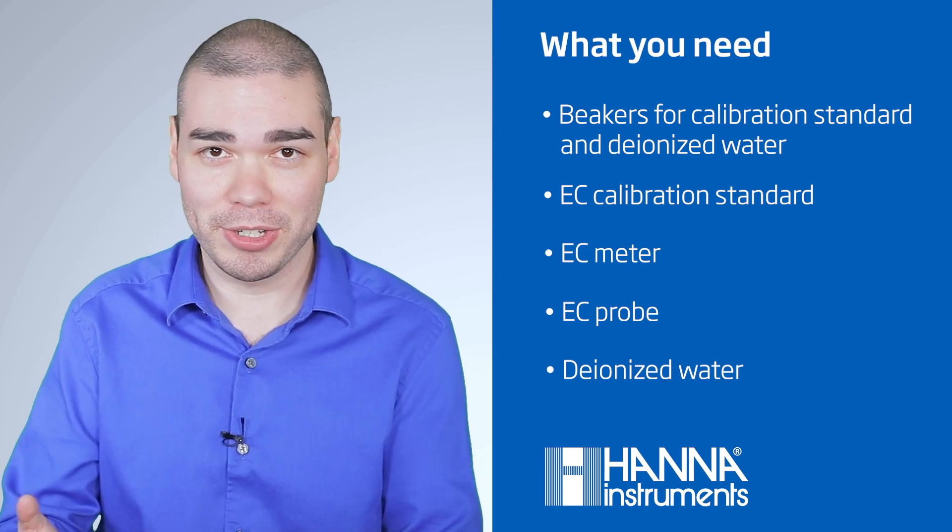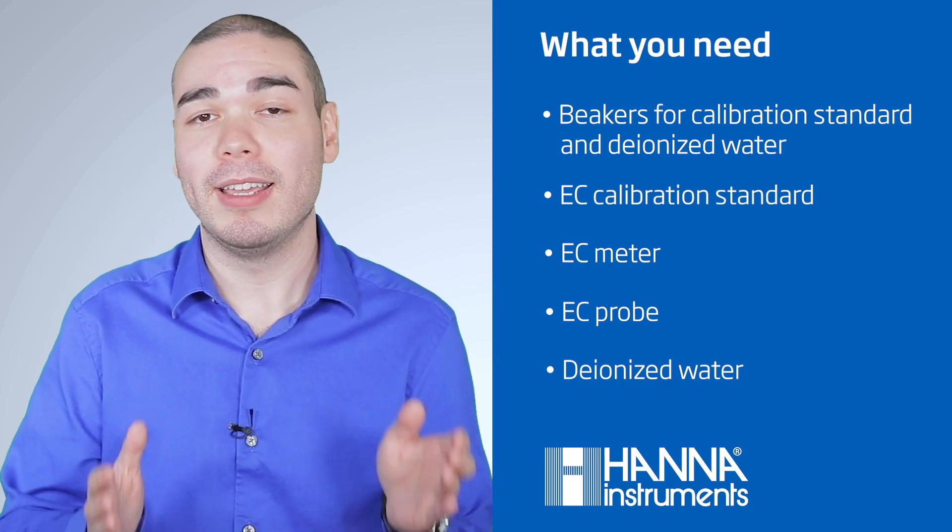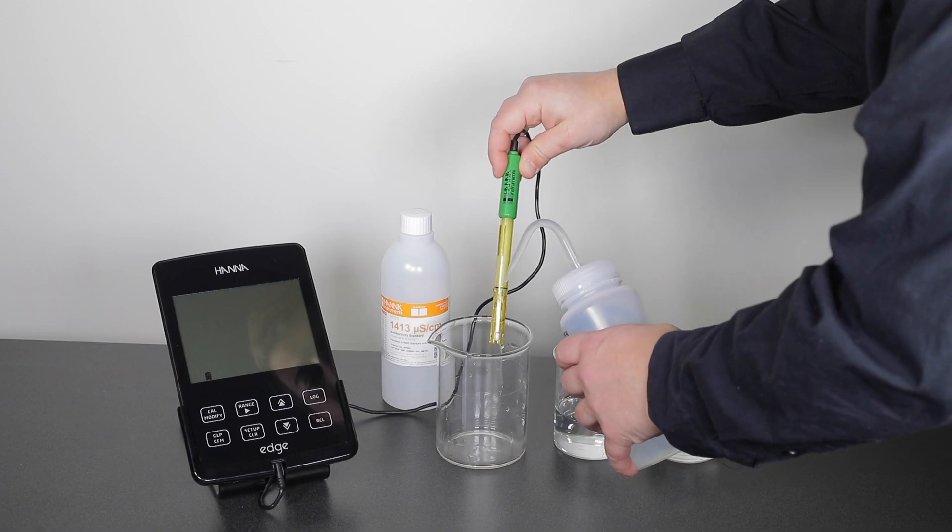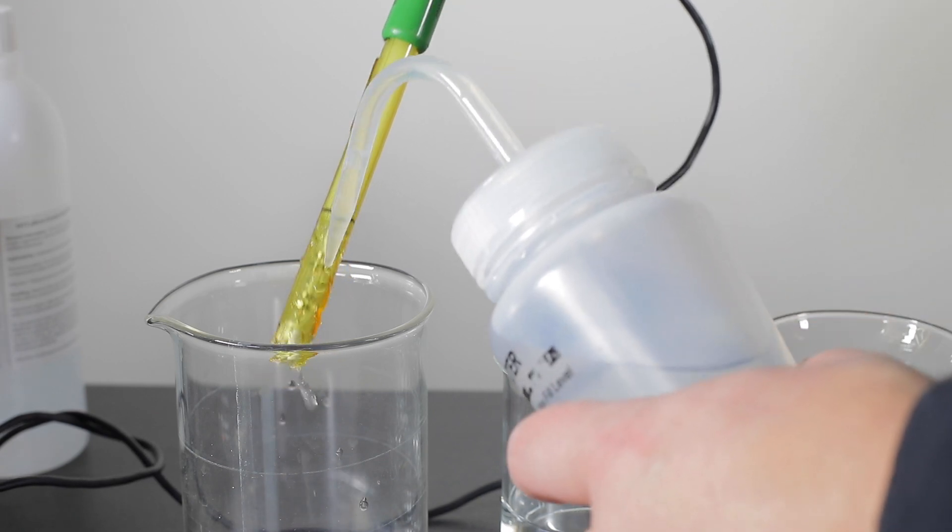When calibrating, we recommend following the subsequent steps. You will need beakers, a calibration standard, a meter, EC probe, and deionized water. Before even placing a probe into the standard, rinse the probe in deionized water.